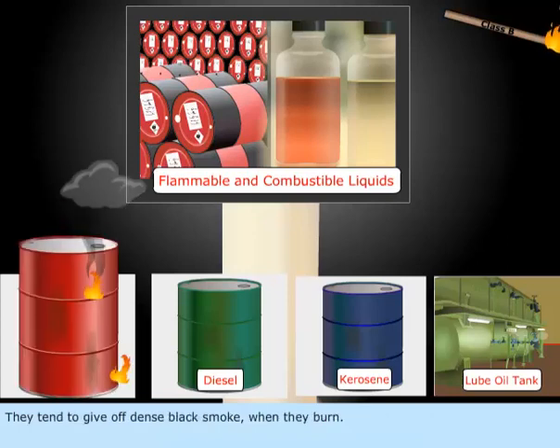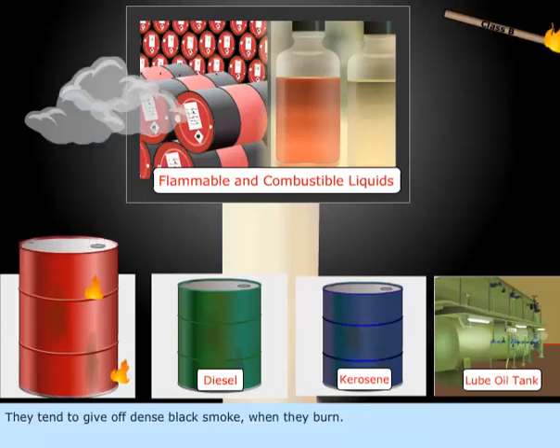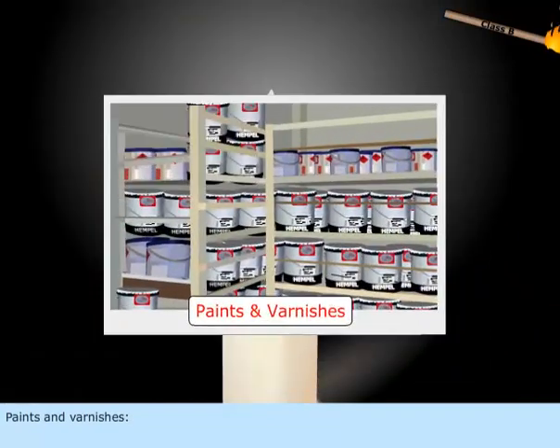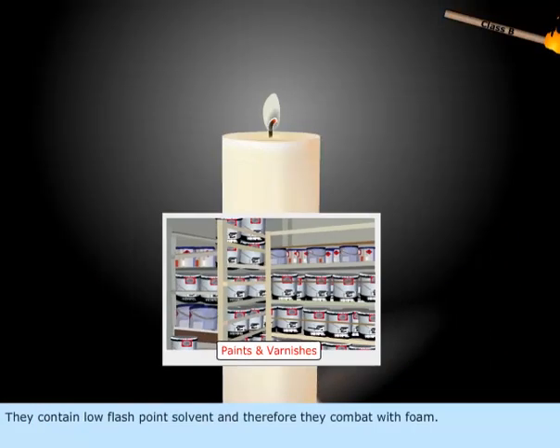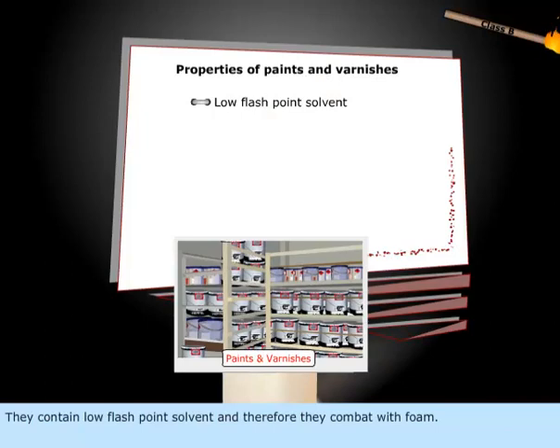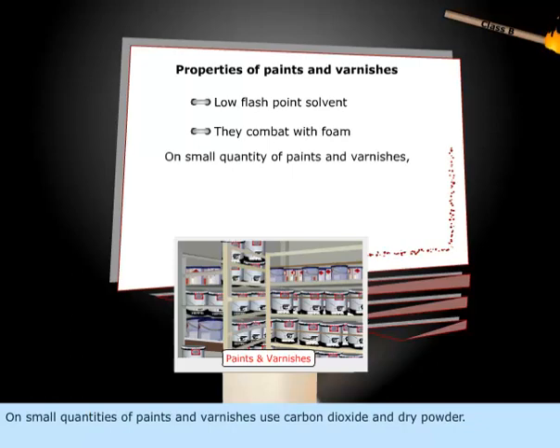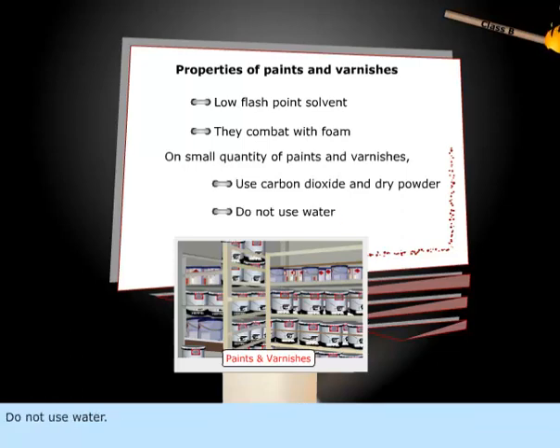Combustible liquids tend to give off a dense black smoke when they burn. Paints and varnishes contain low flashpoint solvent and therefore they are combated with foam. On small quantities of paints and varnishes, use carbon dioxide and dry powder. Do not use water.